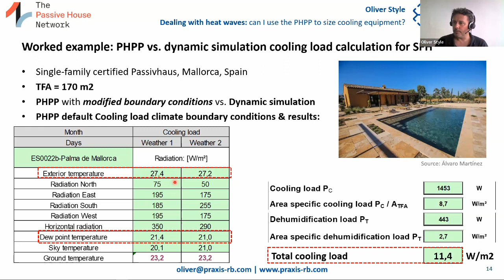So the first mistake is to say, great, I'm going to use that, multiply it by my 170 square meters, and then I have the kilowatts I need in order to tell the installer to put X kilowatts of heat pump in there for cooling, okay? Because these are obviously not peak climate conditions, and we'll also look at occupancy conditions. These are the average over 24 hours, okay, and that's an important distinction because, you know, we've suffered the consequences of that.